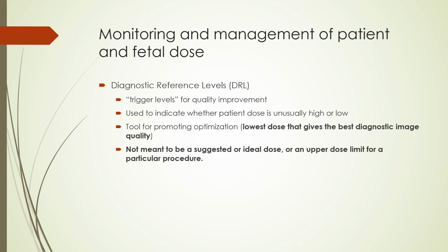Diagnostic reference levels apply to medical exposure, not to occupational and public exposure. Diagnostic reference levels are not a suggested or ideal dose for a particular procedure or an absolute upper limit for dose, but rather represent trigger levels to initiate quality improvement.